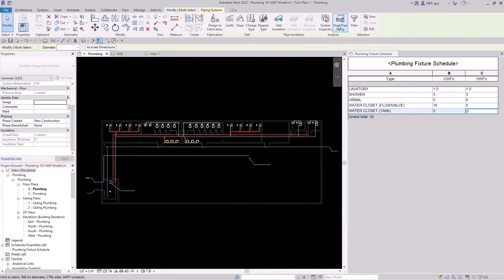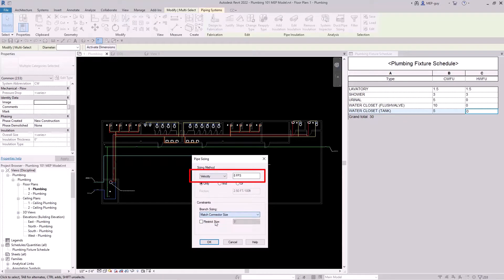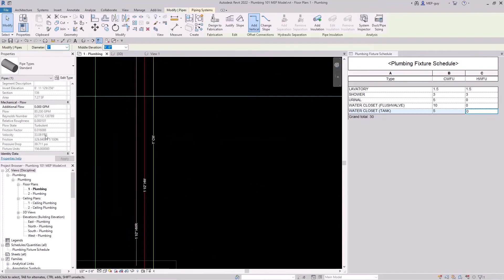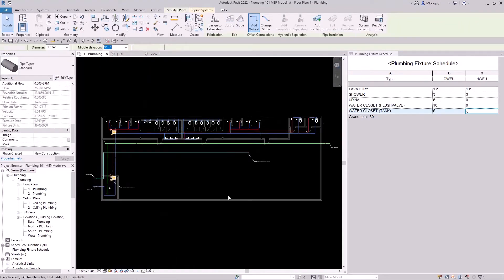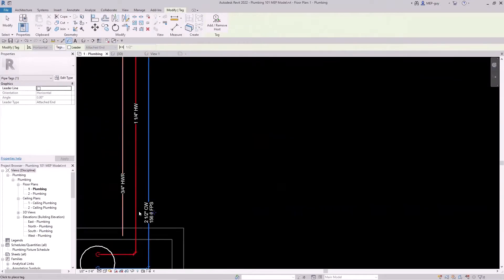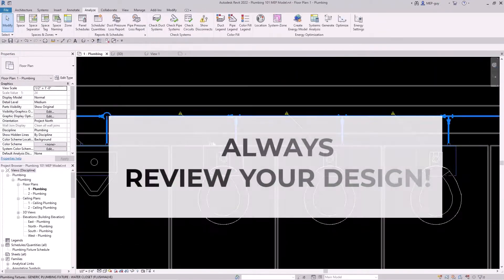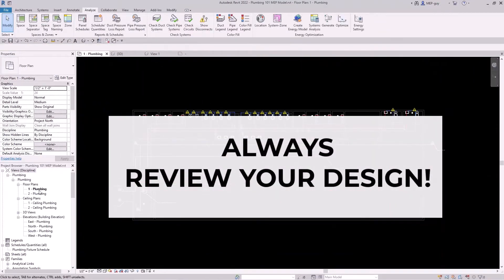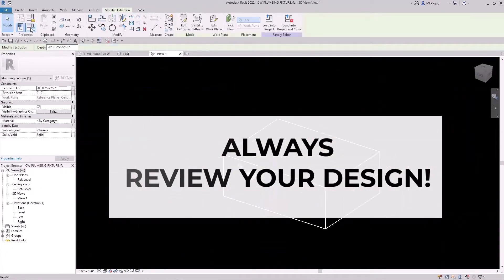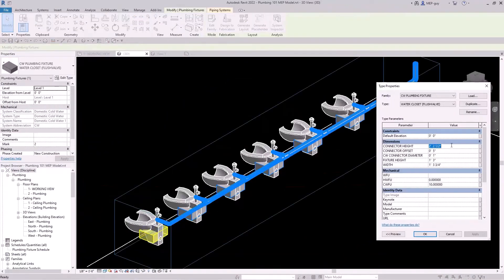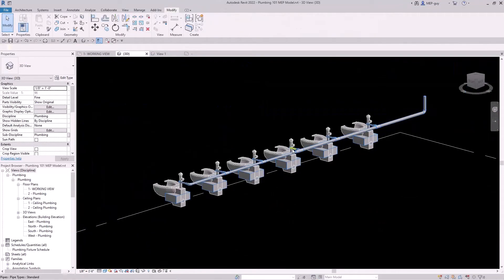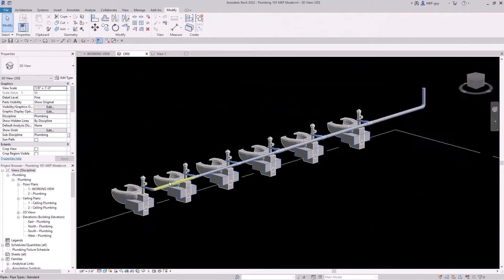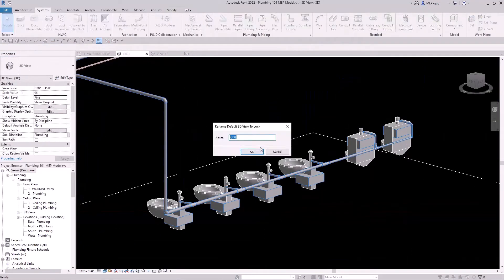Right here I'm showing how to use the automatic sizing tools. We're going to use it to set a specific velocity, which will dictate the size of the piping to each plumbing fixture, using the fixture unit values and the GPMs. Even though there are some automatic calculations going on, it's always a good idea to review the sizes that have been created, as you would do even if you didn't have Revit. Here I'm just showing how to confirm the sizes and verify that the sizes are looking correct.